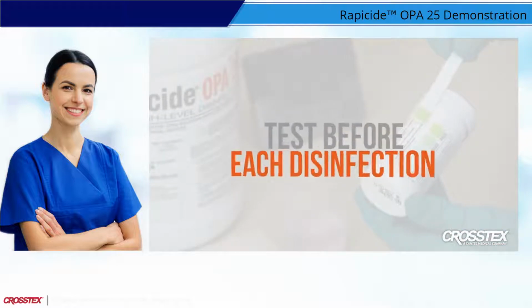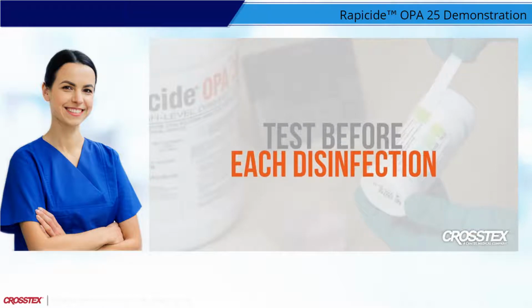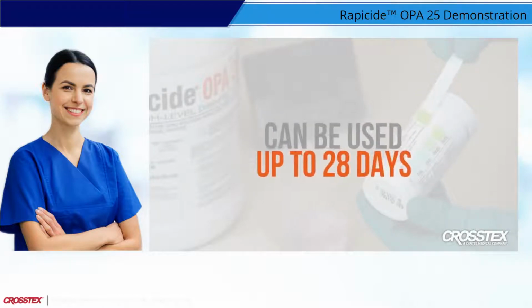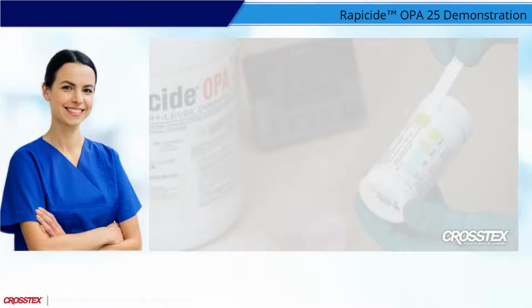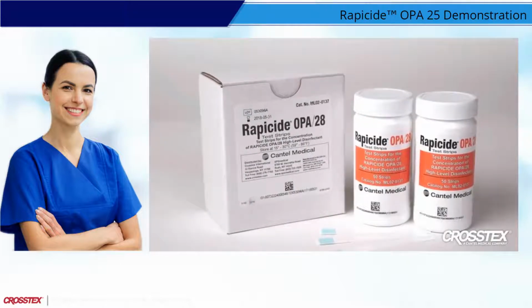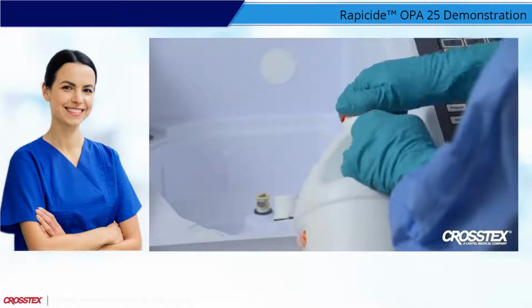Make sure to test the solution before each disinfection. The Rapicide OPA 28 HLD solution can be used for a period up to 28 days, provided that prior to each use, the concentration of OPA in the solution is verified using Rapicide OPA 28 test strips to be above the MRC of 0.35%. The solution must be discarded after 28 days.